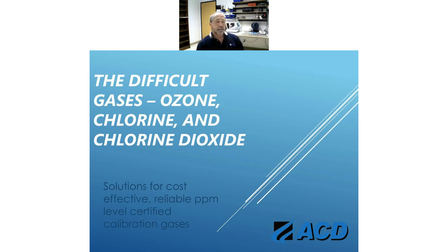And we're going to talk a little bit today about these particular 3 gases. Chlorine dioxide is a gas that if you compress it into a cylinder, it is explosive. So it can't be put into a gas cylinder. Ozone is very reactive, and so is chlorine. So the problem with these gases is they're so reactive, when you put them into an aluminum cylinder, even with a lining, or the inside of the cylinder is trying to be non-reactive as possible, still they tend to react. So we have on-demand gas generators that produce the gas on demand and can be used to calibrate these difficult 3 gases.